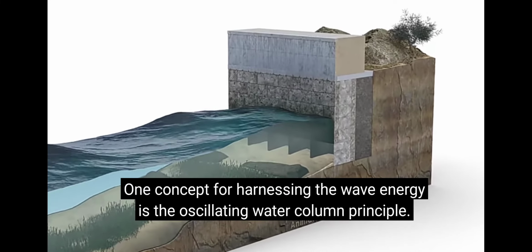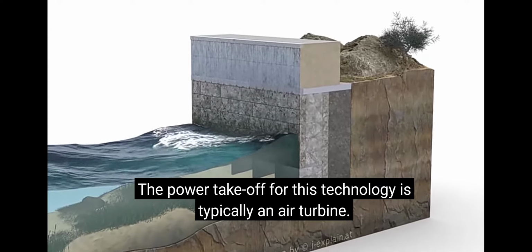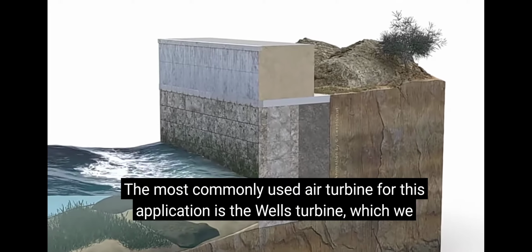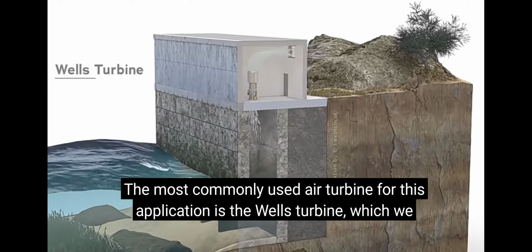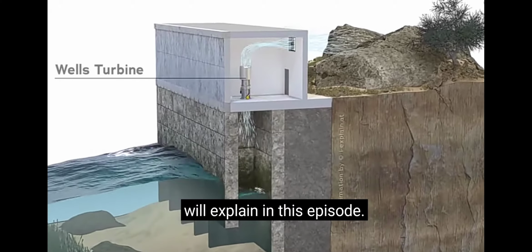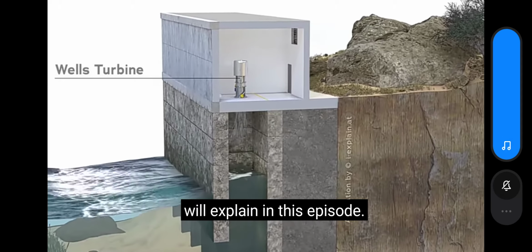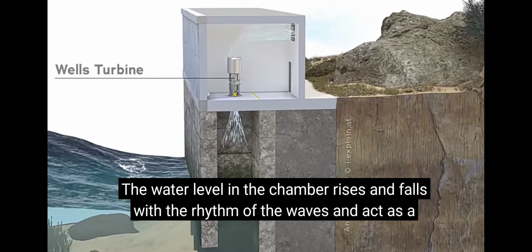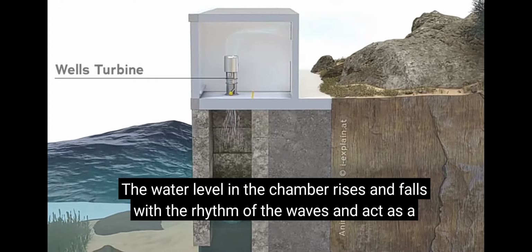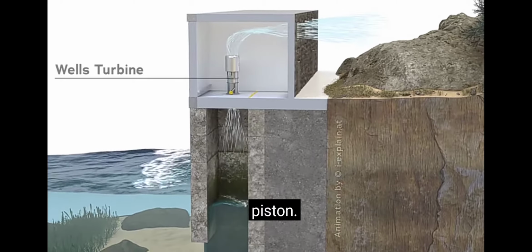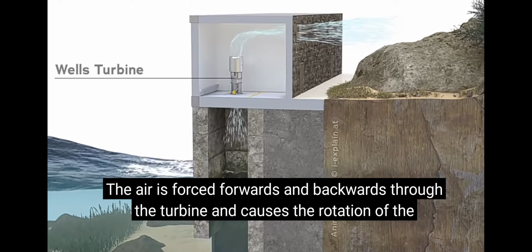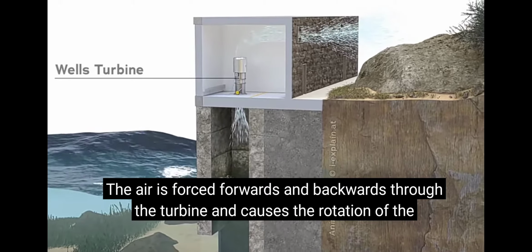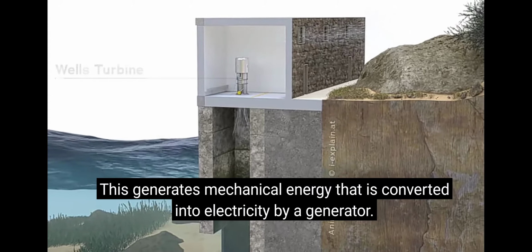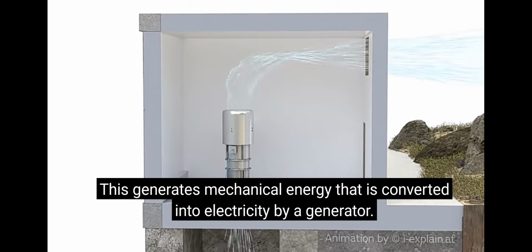Oscillating water column principle. The power takeoff for this technology is typically an air turbine. The most commonly used air turbine for this application is the Wells turbine, which we will explain in this episode. The water level in the chamber rises and falls with the rhythm of the waves and acts as a piston. The air is forced forwards and backwards through the turbine and causes the rotation of the turbine. This generates mechanical energy that is converted into electricity by a generator.